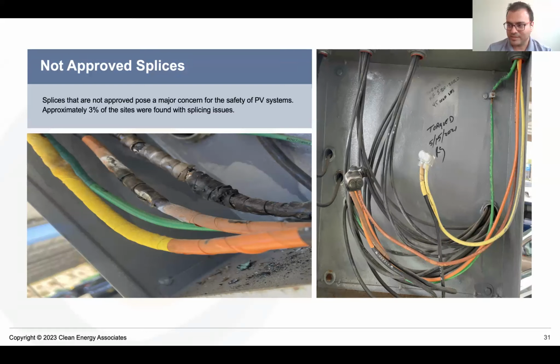These splices are not recommended. If they have to happen, they need to undergo a proper approval process. A lot of these decisions are made on site by a technician or electrician. For this specific scenario, no one knew the splices existed in this box, no one knew there was something bad going on in there. Luckily, we found this before it could turn into a major incident.